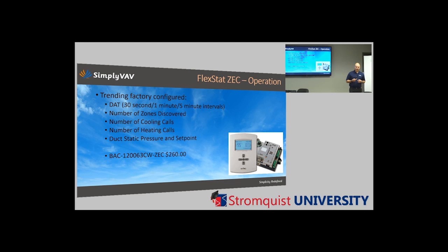The other feature that's good for debug, so if you're looking at this through BACnet or a JACE, there's factory configured trending for DAT in a few different intervals, so you can see trends. You can make sure your equipment's staging up and staging down properly. We trend the number of zones and the heating cooling demands. And we also trend duct static pressure and both the set point and feedback.